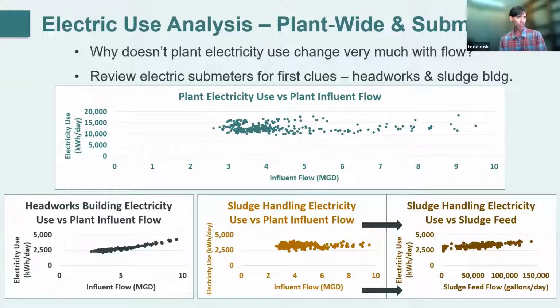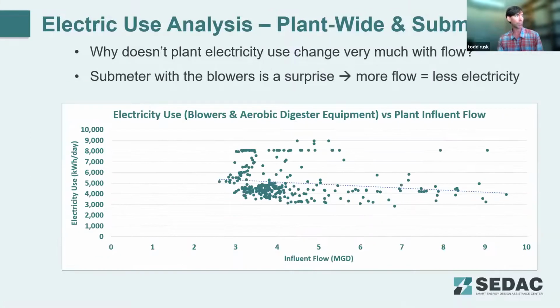The thing we noticed was we scratched that one a bit more because they were interested in the sludge handling building. This graph on the lower right shows what the sludge handling area uses for electricity versus the sludge feed - how much sludge solids are coming out of the process into that building. What we see is a discernible increase. We might like to see a bit more variation, but it makes sense - more sludge flow coming into the area means more electricity use. But still, we don't quite have the answer - why isn't the overall plant responding the way we expect?